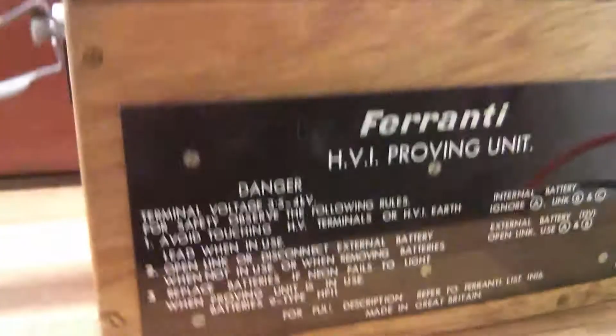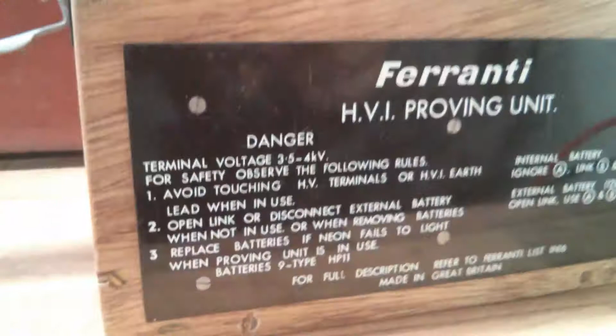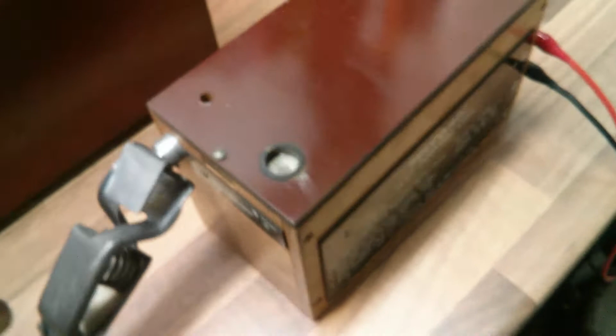Right, aim the probe down onto there, and you'll see when I push down. Not sure if you can hear that - that's testing, on the 5 kV scale, the bottom scale the way we're looking. That's about just around 4 kV there, which is what it's designed to output - 3.5 to 4 kV terminal voltage. Seems to be working pretty cool, pretty fine, so I'll disconnect that.